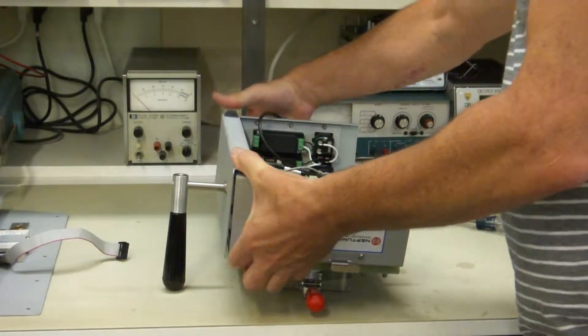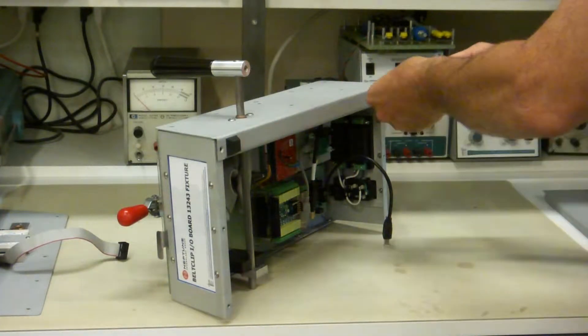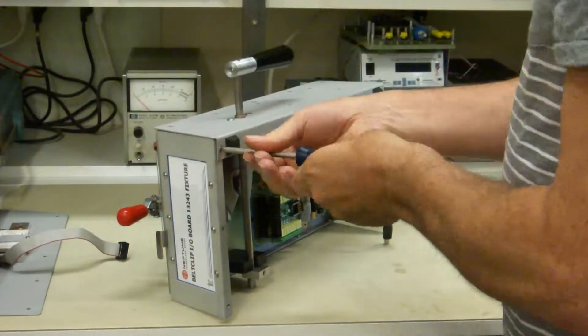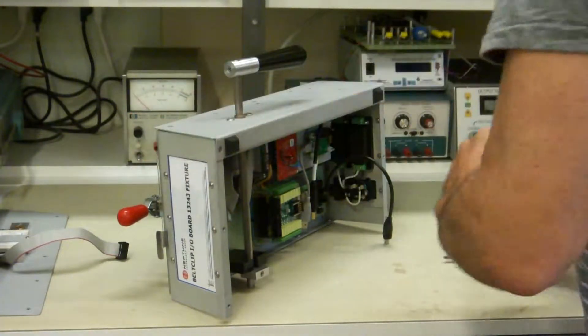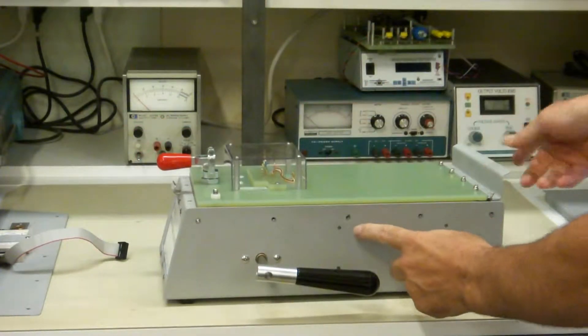Just jiggle it a little bit there and put it on its edge. What I like to do is put these two end flat head screws in kind of loose so everything will self-align in the end, and then tighten it all down. Also pull this handle back once you have it in — that relieves the pressure on the spring plates, so there's no pressure trying to push you out of doing what you're doing. Then the next screw I like to put in is this middle one.